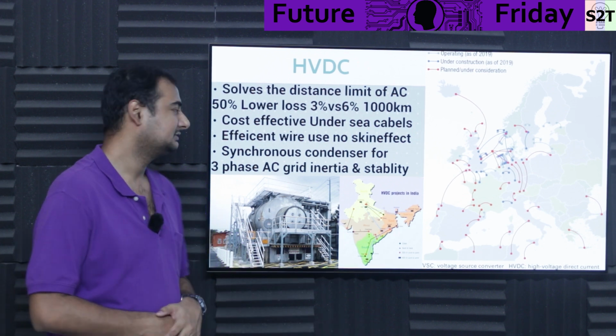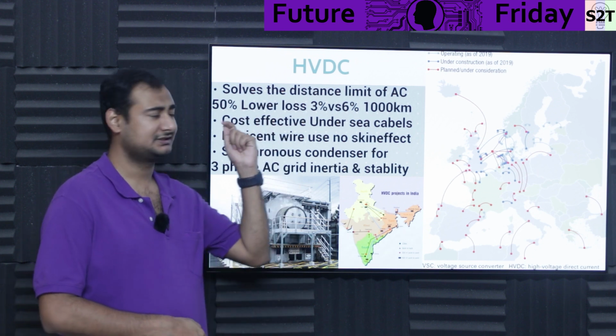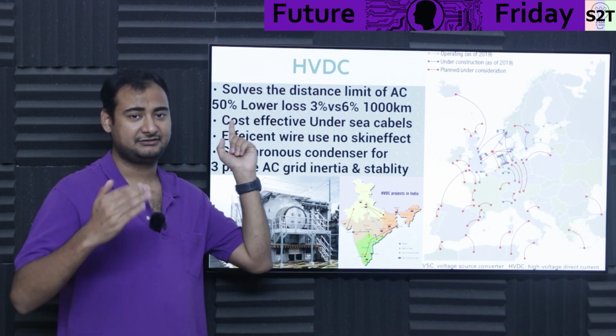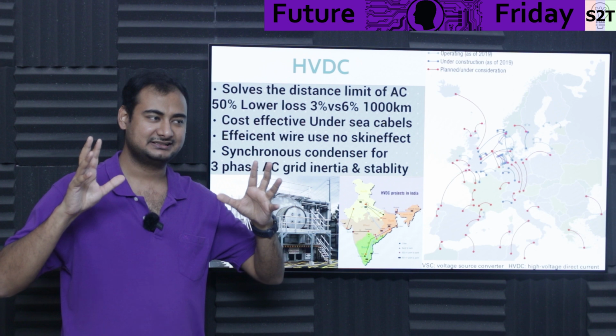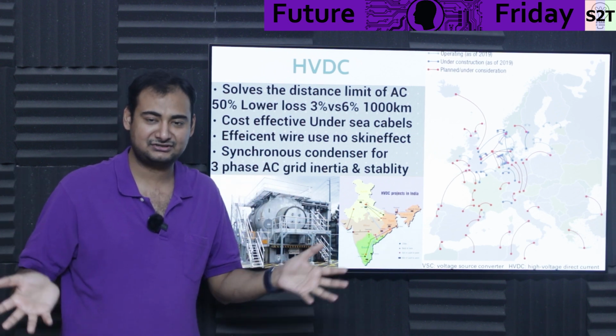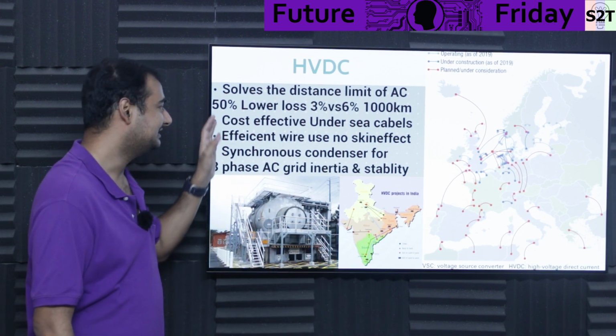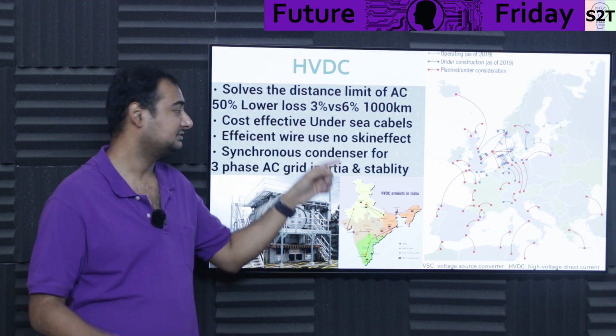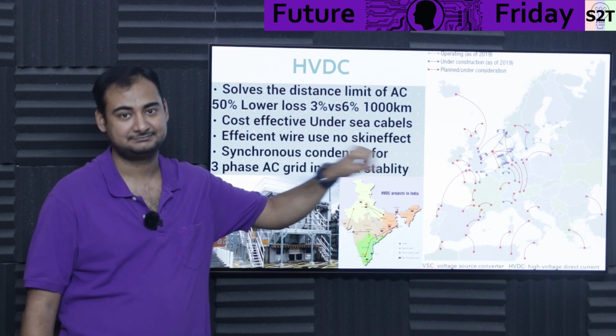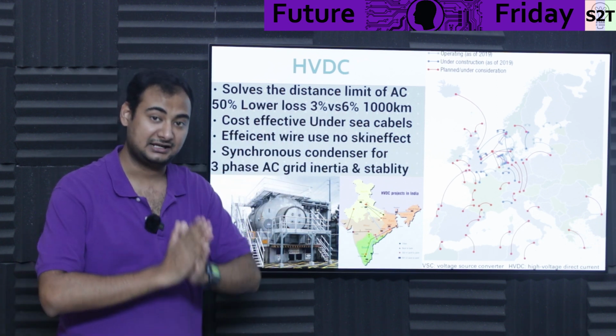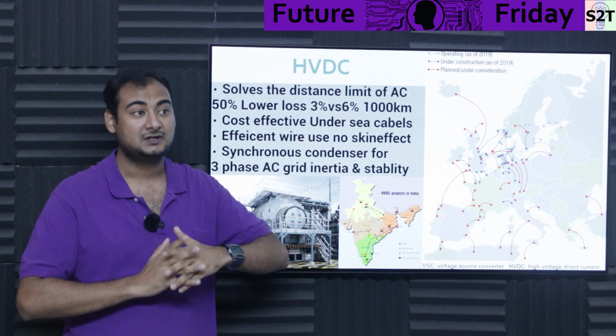Why? Capacitance loss. That's why you'll hear it has 50% less loss, but that number looks odd - are we wasting 50% of AC power? No. What it actually means is, instead of having 6% loss, you have 3% loss per 1,000 kilometers. That's why an HVDC link can go very far.